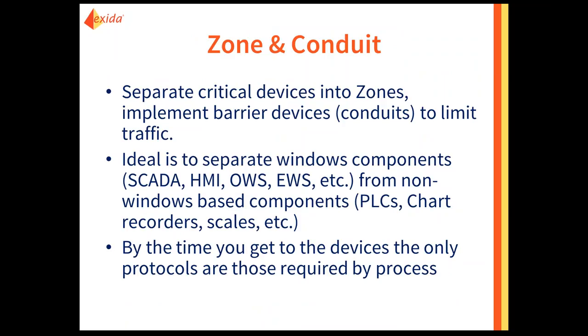Once you begin the actual work, you separate your network into critical zones and use a barrier device — a conduit — to limit traffic flowing from zone to zone. My strong recommendation is to separate your Windows components, such as SCADA systems, HMIs, and operator workstations, from non-Windows devices like PLCs, chart recorders, and scales — devices that do not like the broadcast chatter that Windows produces on the network.